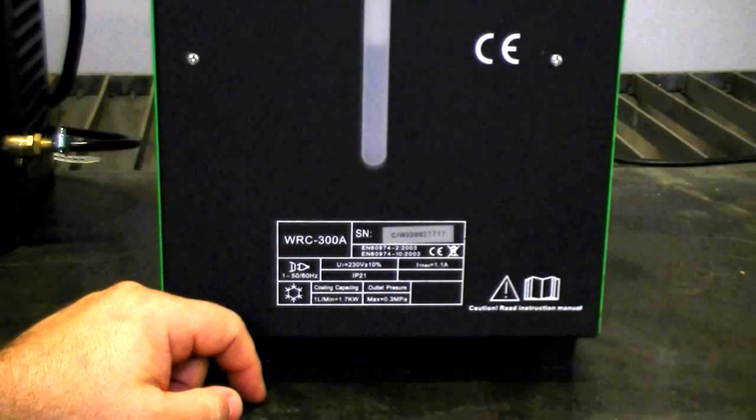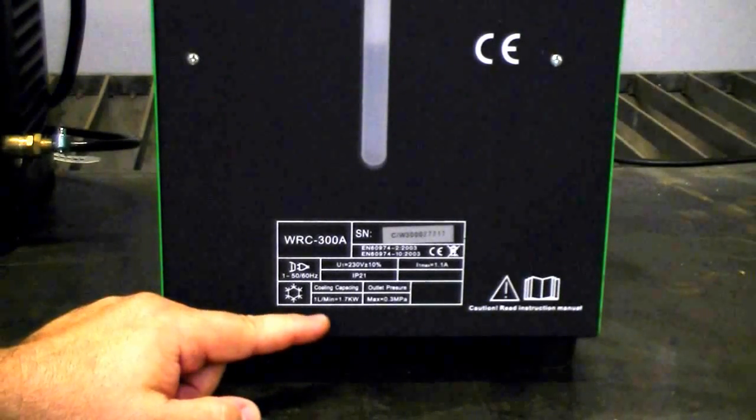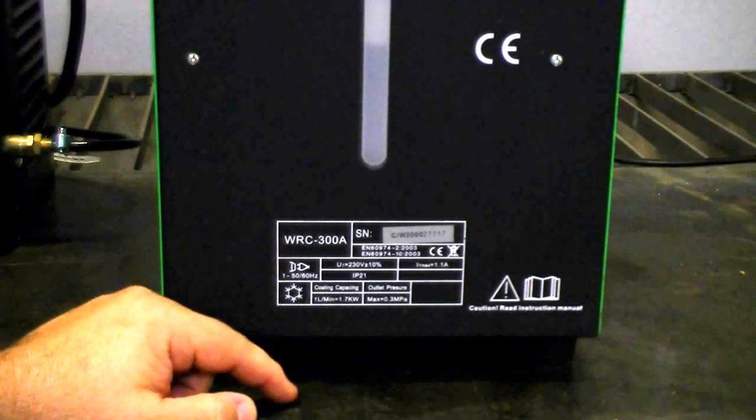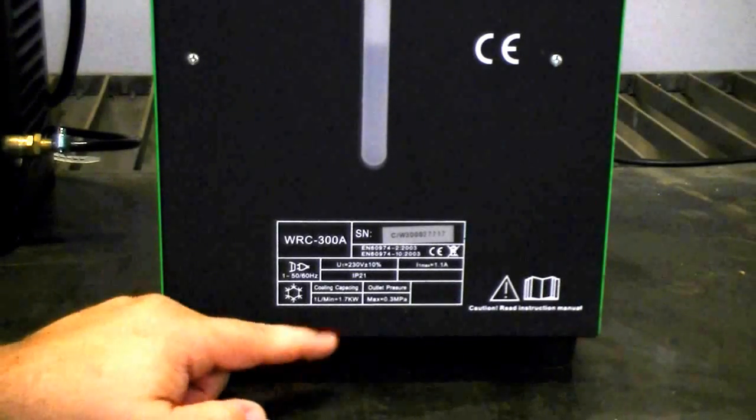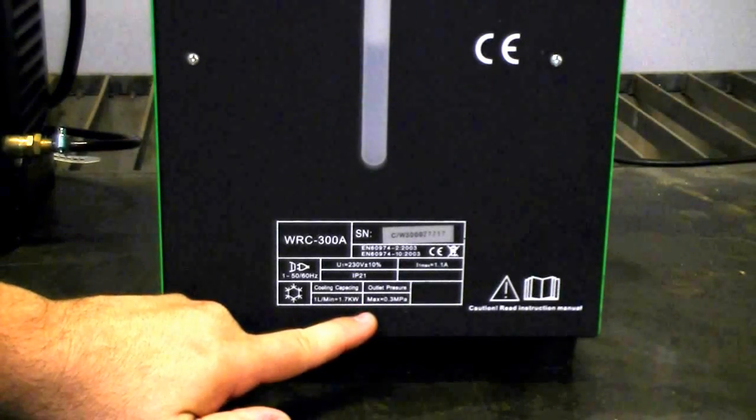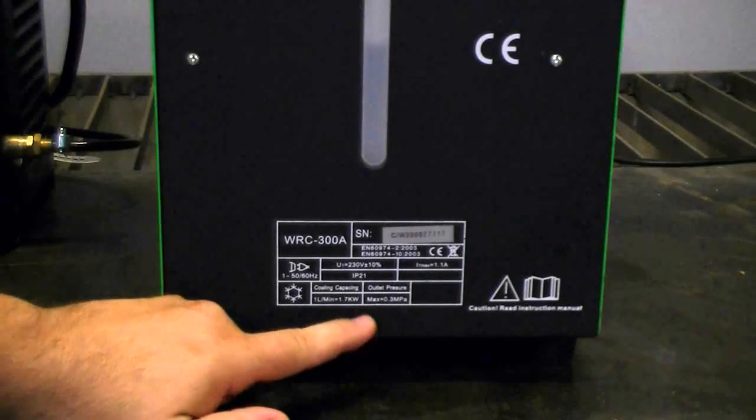This unit has a cooling of about 1 liter per minute. That's enough to get you about 1.7 kW worth of cooling. It also has a pressure of about 0.3 MPA, or that's about 45 psi.